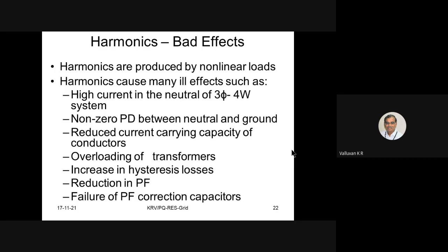But if the load has harmonics, the current in the neutral wire can be as high as 2 times that of a phase or line wire, which is very, very surprising. In one of the consultancy works we carried out, when we measured the neutral current, it was 2 times the phase current. So the cable got punctured. Three cores of equal size are used for the three phases, but only half the size is used for neutral because it is not supposed to carry any current. But if it carries twice the current, then you can imagine the I square R loss that creates a lot of heating, and the cable gets punctured. That is because of harmonics.